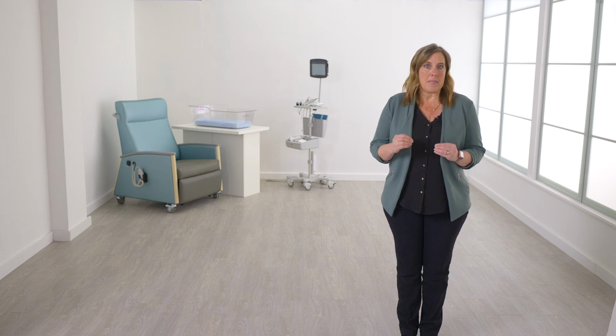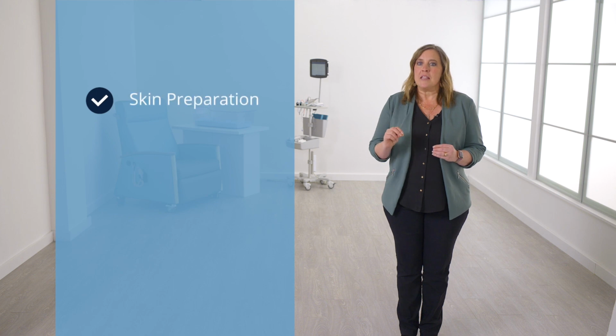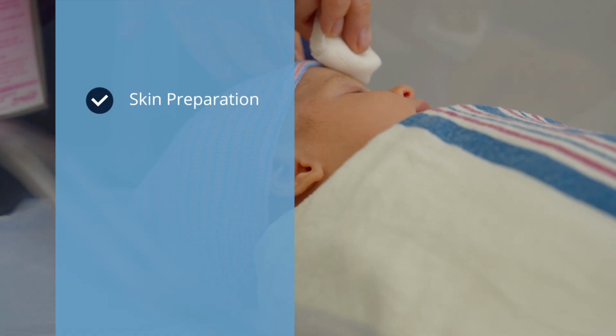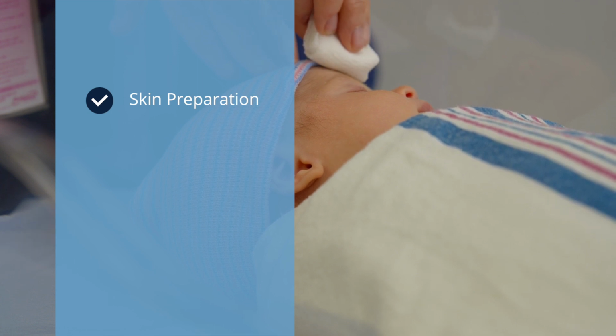The GSI Novus is optimized for fast and efficient newborn hearing screening. In addition to ensuring your Novus is working properly, there are 3 key factors for successfully screening a baby. Number 1, skin preparation. The impedance between the skin and electrodes can make or break a test. It was indicated in this tutorial that the impedance should be below 10 kiloohms for testing.